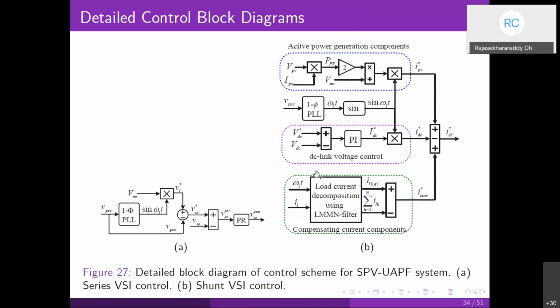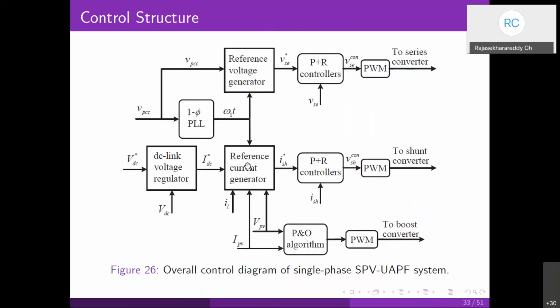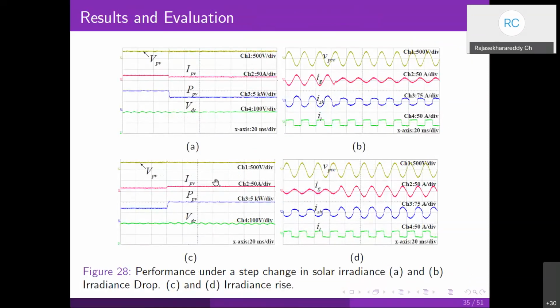Okay, so this shunt converter control configuration is the same as that of the previous case. There is nothing new here. If you look at the series converter control, what I'm doing is generating reference load voltages and comparing them with the PCC voltages. The difference should be the series converter injected voltage. Based on the difference between the actual series injected voltage and the reference series converter voltage, we get an error. That error is processed with PR, proportional plus resonant controllers, to generate PWM modulating waveforms for the series converter. Then we have experimental results.